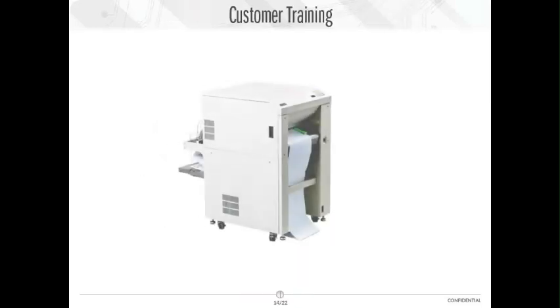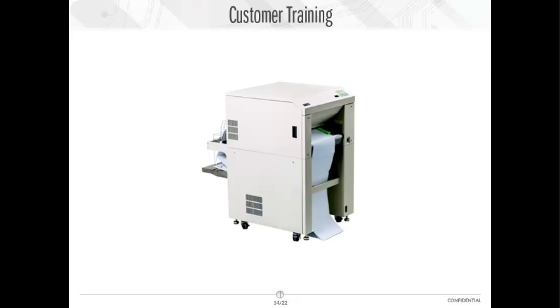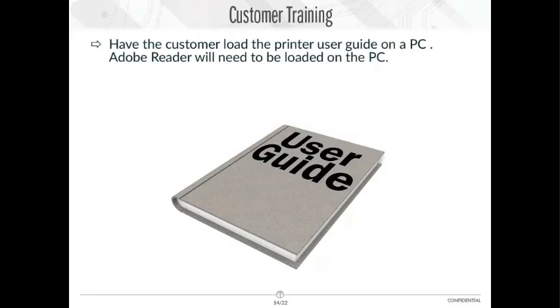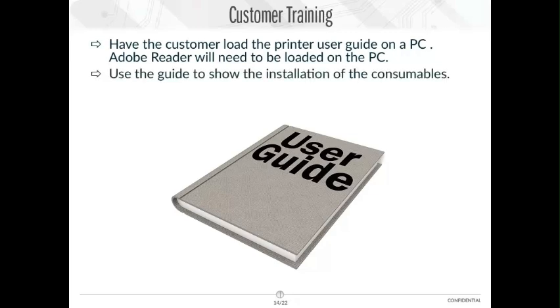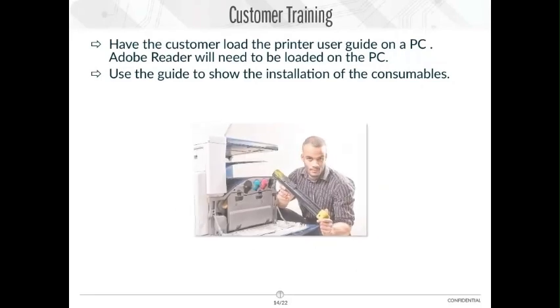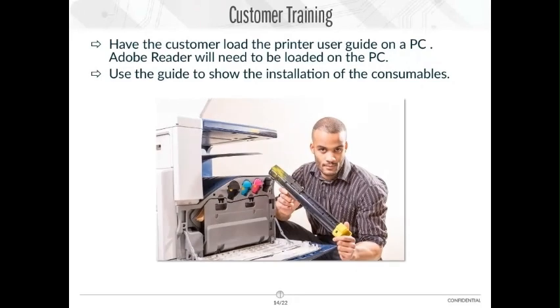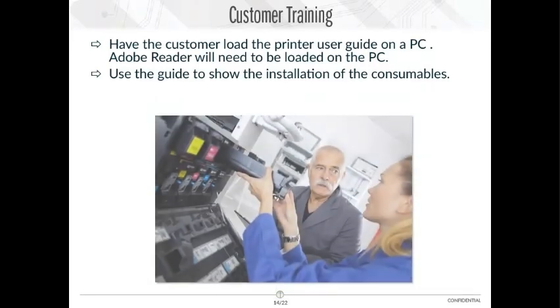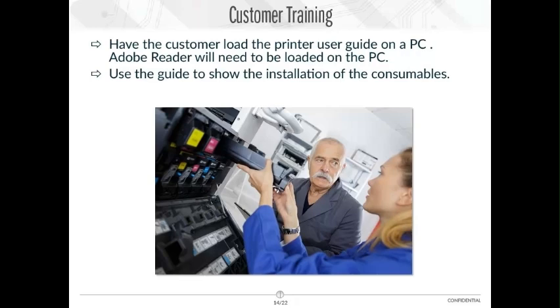After completing the installation of the printer, conduct a customer training session. Please ask the customer to have the user's guide loaded on a nearby PC. This will require Adobe Reader to be installed on the PC. Please follow the user's guide for the steps for all customer replaceable items, proper use and care of the product. The TSR should perform loading of consumables, to demonstrate to the customer how it is done. Then, the customer should load each of the consumables to verify that the instructions were understood. All questions should be covered at this time, to ensure that the customer is comfortable with replacing the consumables.